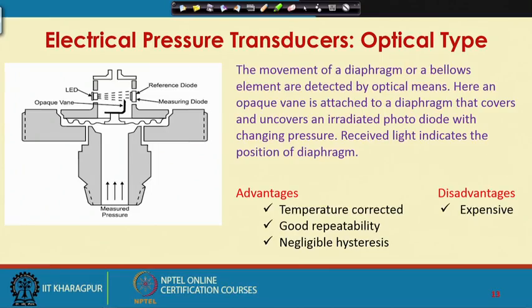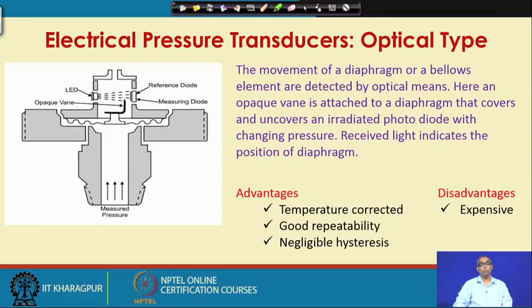Next, let us talk about electrical pressure transducers that are optical type. These are more recent electrical pressure transducers. Here again we make use of a diaphragm or bellows as a primary sensor. Now, this is, let us say, a diaphragm, and I apply the pressure to be measured here.